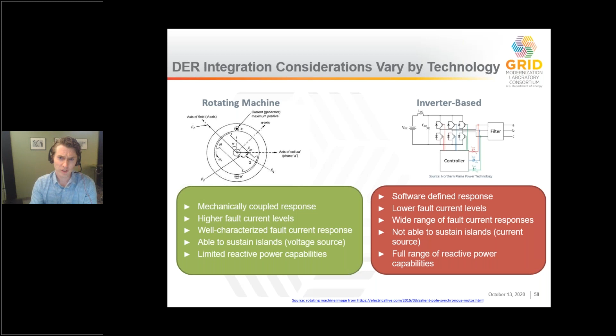And then inverters, since they're software-defined devices, the fault current response when there's a problem on the grid greatly varies by the particular manufacturer and how that device was designed. Grid interactive inverters aren't able to sustain an island or energize loads that are disconnected from the broader grid. They're really relying on that fundamental voltage from the grid in order to operate and supply current into the system. But they are, again, very flexible, so they have a wide range of these reactive power capabilities, which we'll talk about in the context of smart inverter or advanced inverter functions. So next slide, please.